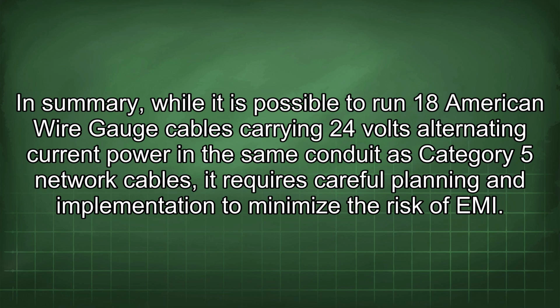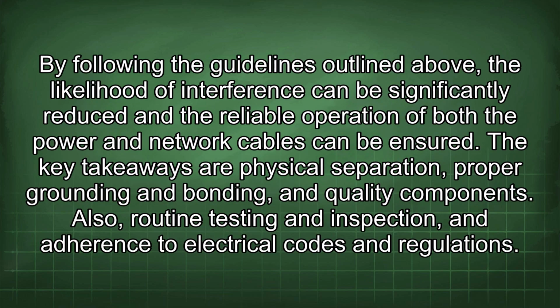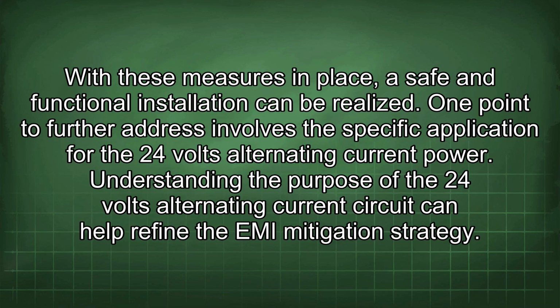In summary, while it is possible to run 18 American wire gauge cables carrying 24 volts alternating current power in the same conduit as Category 5 network cables, it requires careful planning and implementation to minimize the risk of EMI. By following the guidelines outlined above, the likelihood of interference can be significantly reduced and the reliable operation of both the power and network cables can be ensured. The key takeaways are physical separation, proper grounding and bonding, and quality components. Also, routine testing and inspection, and adherence to electrical codes and regulations. With these measures in place, a safe and functional installation can be realized.